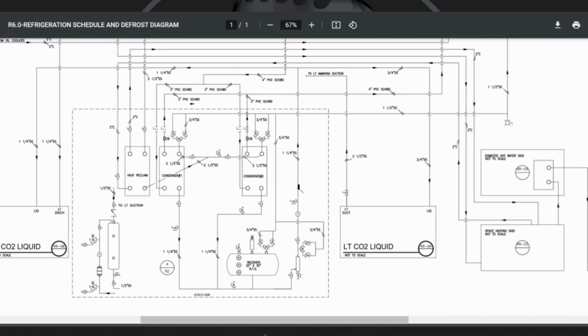And just remember, guys, it has to be non-brass, non-copper because we are dealing with ammonia here. Yes. So if I had to guess, those expansion valves are probably flanged in there, right? For serviceability. No, they're welded. Oh, they are. Wow. We don't want any flanges. They're welded, but they do come apart. So if the head goes bad, we can replace the head. I can't remember what they call them. It's got a solenoid, a shutoff valve, and an expansion valve all in one casting. I know exactly what you're talking about. And you can bolt them together any way you want, in any sequence you want. They use the same welded body. It's really a very convenient device.